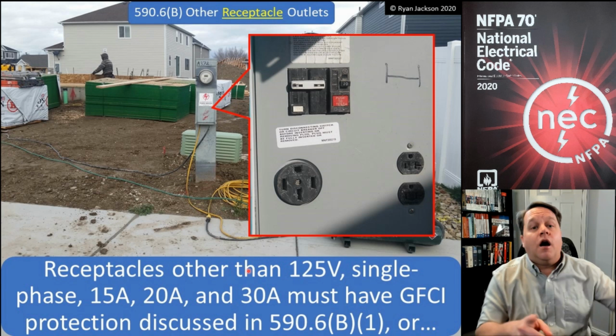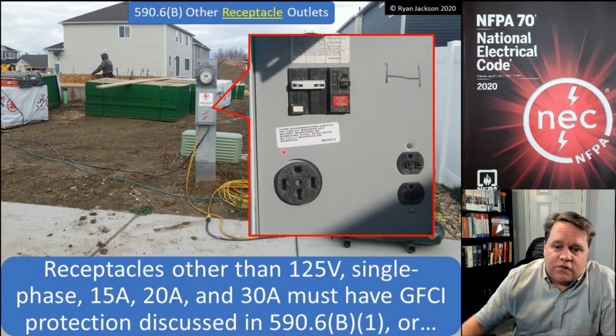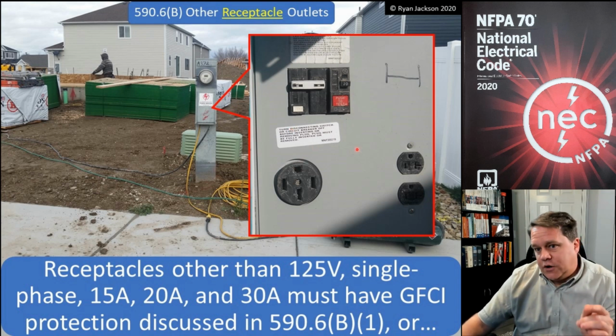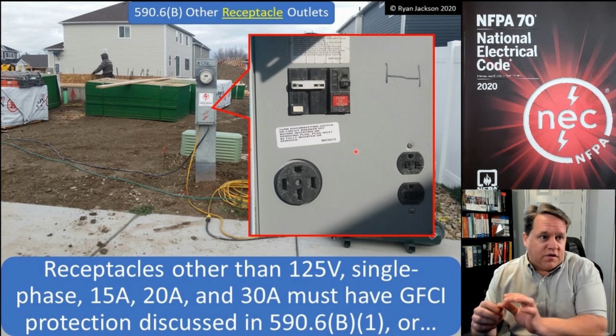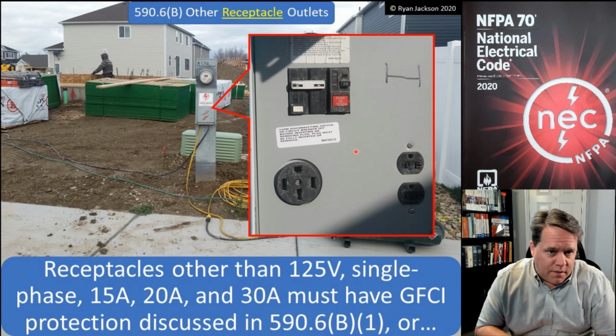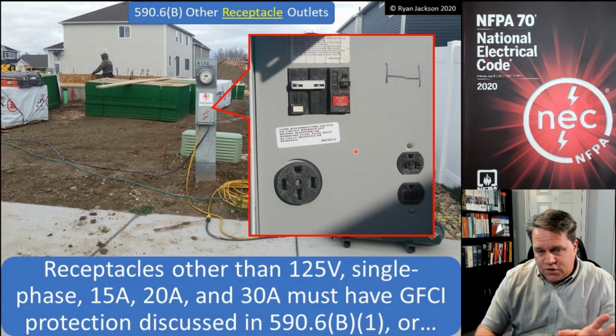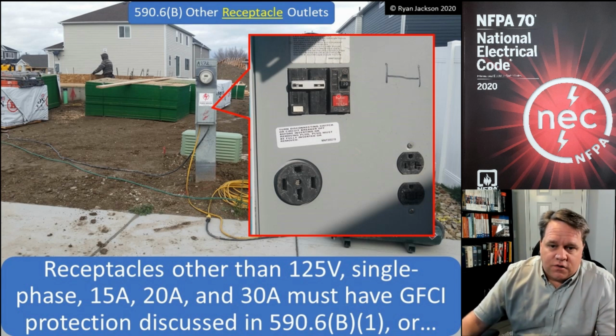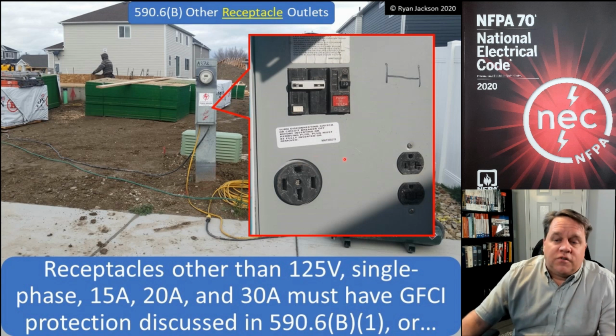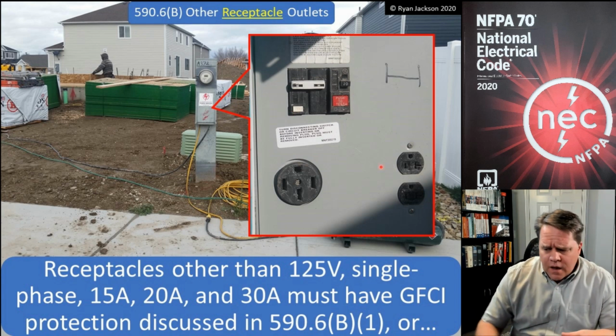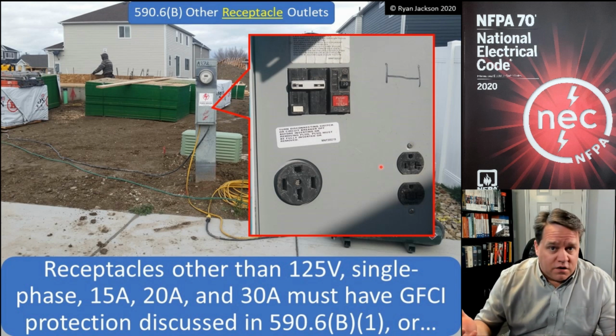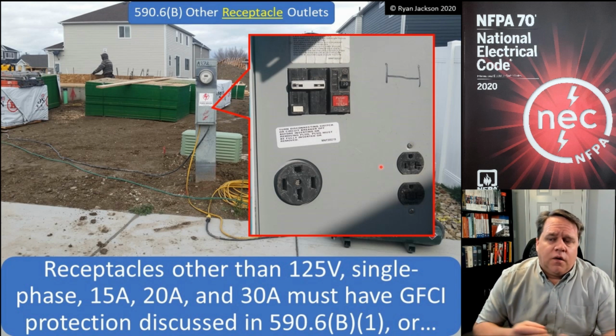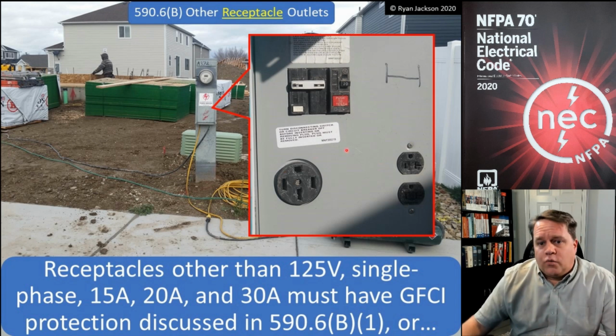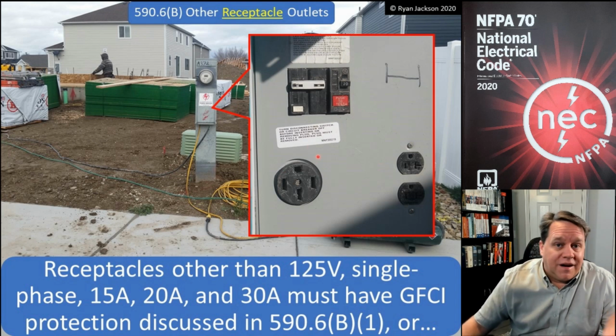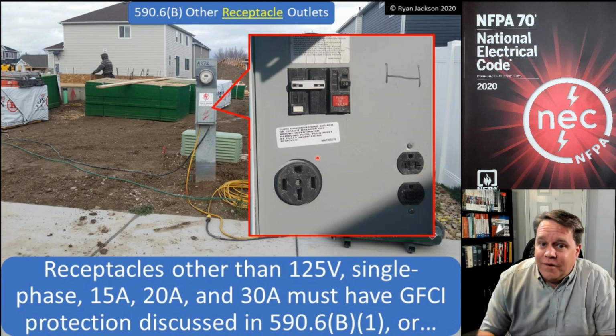That's the rule. Other receptacles, like the one here in the photograph, this 250 volt, 50 amp rated receptacle, those also have to have GFCI protection, or a system that we call the Assured Equipment Grounding Conductor Program. So let's start with option 1, which is GFCI protection. You have to have GFCI protection. This is a GFCI breaker for this 250 volt receptacle that is absolutely required. It's been required for at least 20 years off the top of my head. I know when I travel around, there's a lot of places that don't realize that this is a requirement and has been a requirement for a very long time.